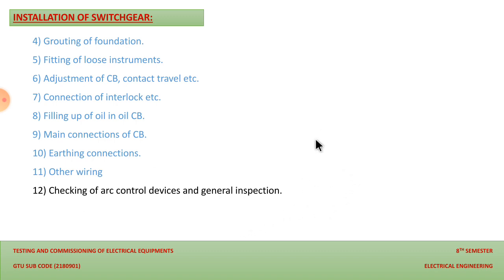So yes, when we operate our circuit breaker and/or switchgear, due to the operation of these devices, an arc will be produced. So we have to check the utility of the arc control devices in priority, because if we cannot extinguish the arc, there might be a chance of fire while the switchgear operates.